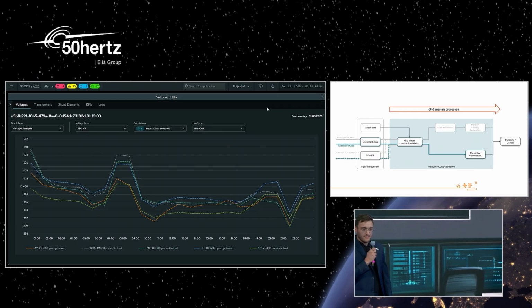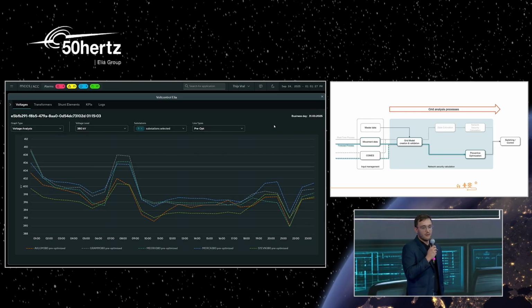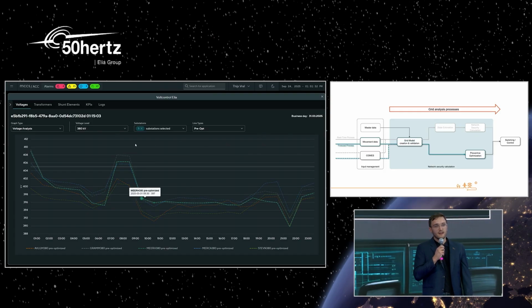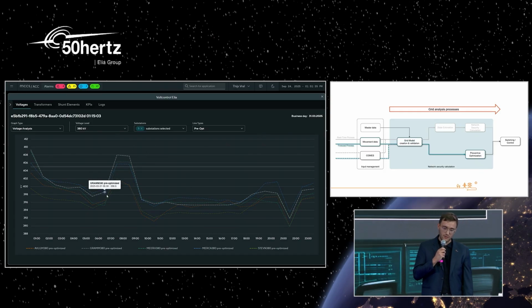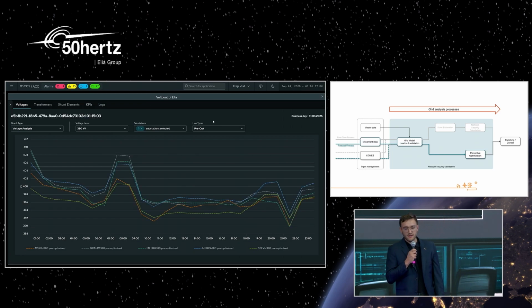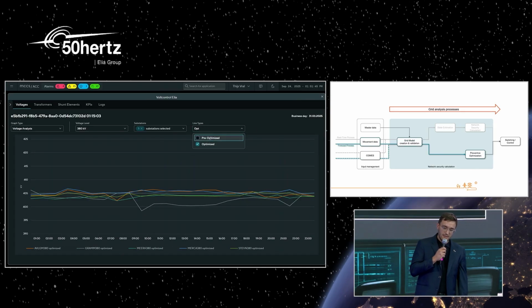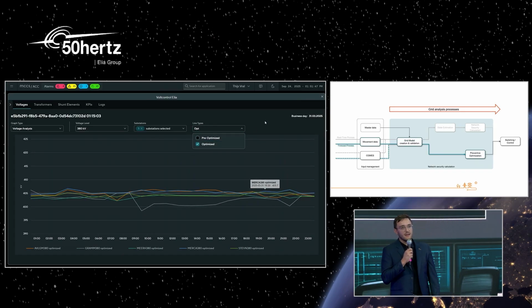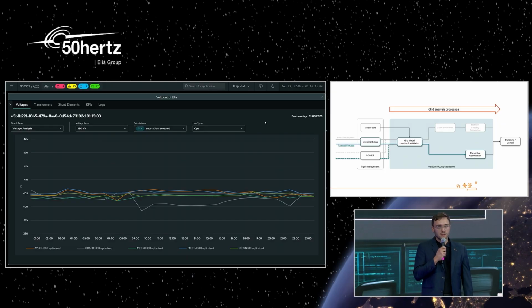I brought you here today a voltage profile from the Belgian power grid from the beginning of this year, for a selection of certain substations. As you can see, we have quite a large peak in the morning hours between 7 and 9, and a small dip in the evening hours. If we now turn on the optimized voltage profiles, we can clearly see that our optimization has done what it should: it flattened the volatility and the peaks, and we are operating much closer to the target voltage of 405 kilovolts.